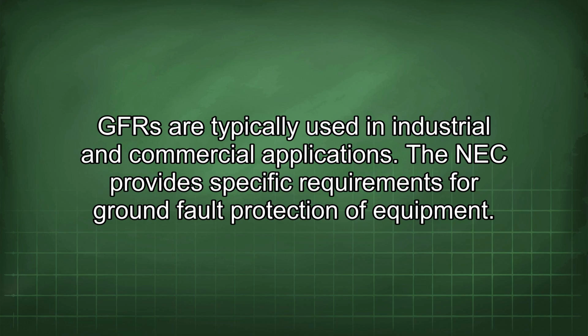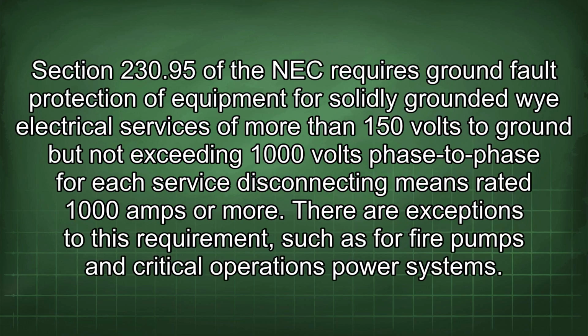The NEC provides specific requirements for ground fault protection of equipment. Section 230.95 of the NEC requires ground fault protection of equipment for solidly grounded wye electrical services of more than 150 volts to ground but not exceeding 1000 volts phase to phase for each service disconnecting means rated 1000 amps or more. There are exceptions to this requirement, such as for fire pumps and critical operations power systems.